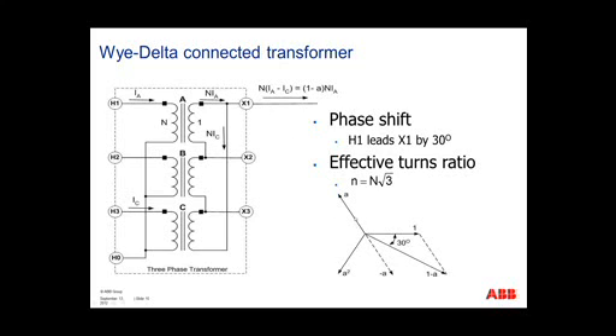If we plot this vectorially, we can see that if we lay A phase currents at 0 degrees, C phase currents at 120 degrees, we take the negative of that, negative C, and we add these vectors together, we can see a resulting vector of 1 minus A. This gives us a 30 degree shift, and this shift is lagging A phase by 30 degrees.